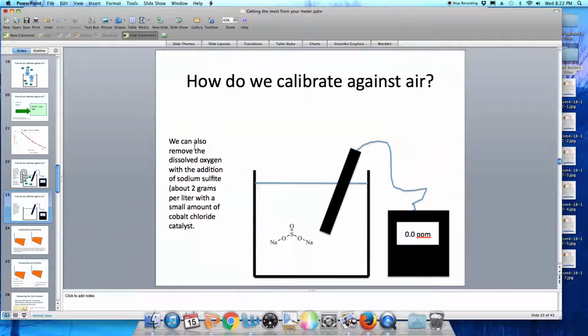We can also remove the dissolved oxygen using sodium sulfite, about 2 grams per liter, and add a small pinch of cobalt chloride to serve as a catalyst. The sodium sulfite will completely remove all of the dissolved oxygen from the water, and your meter should read 0 parts per million dissolved oxygen, or at the very least less than 0.3 parts per million.